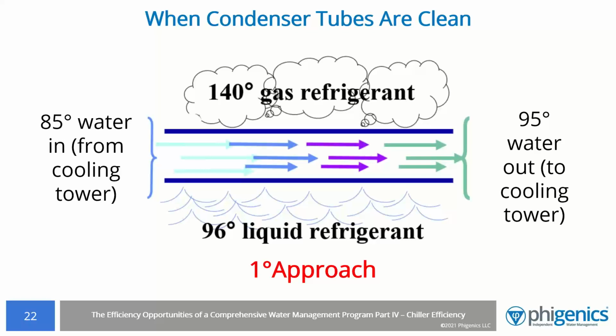So in this case, we're dripping off the tubes at 96 degrees. That's our 1-degree approach that we're looking for. Ideal conditions, full load, clean tubes, 1-degree approach. Keep in mind too that if we were running at a 50% load, we would expect the approach to be half of what you see at 100% load. So at 50% load, a 1/2-degree approach would not be unusual. It would be expected. Next slide, Mike.